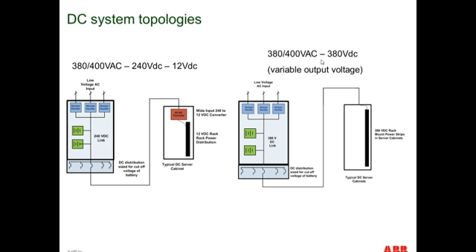They also have a variable output voltage. So in any of these DC systems, including the 48 volt topology, if you're not regulating the battery bus voltage, you have to oversize all of your branch circuit feeders, your conductors, and increase the number of terminations, which all impact cost, reliability, constructability. They all need to be sized for the maximum current that you would see at the discharge cutoff voltage of the battery string. So in essence, you're building roughly a 28% larger power distribution infrastructure with respect to cabling and so forth to accommodate an event, in our industry, an outage that happens 0.001% or less of the time. And we don't believe that that's a very good capital investment cost, but it is the way people are constructing these systems. So hopefully today you'll walk away with a better idea of some of the other options that are out in the world.